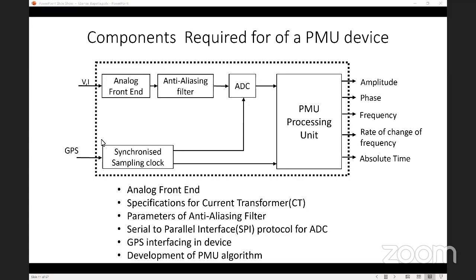From the CT and PT, you get a reduced voltage, maybe to 110 volts—that's usually the range. The secondary of the PT will be either 110 volts or maybe 60 volts, depending on the CTs you use. But industry practice in power engineering is to use 110 volts as the PT secondary. Of course, low power CTs can directly give you either 5 volts or 10 volts, based on what you want.